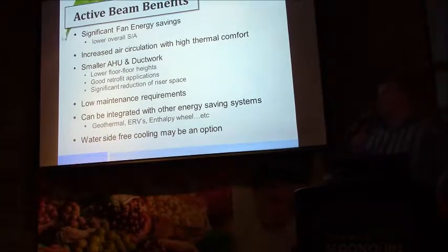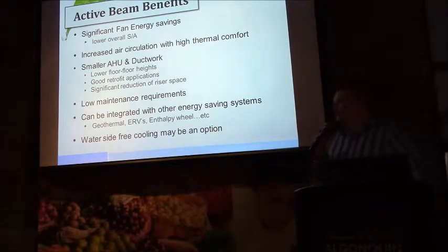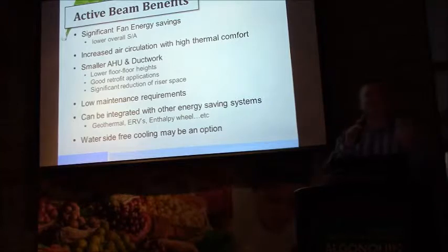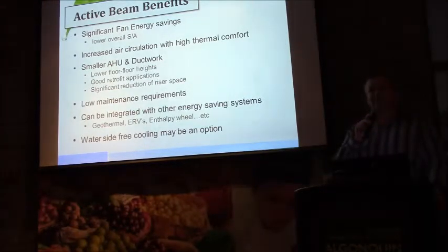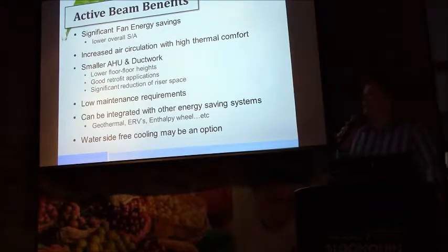And frankly, very affordable. Beams today are running neck and neck in terms of installed costs with a conventional fan coil system. There are exceptions to that, of course, in terms of controls. The more elaborate the controls, obviously, the larger the cost, and the more control resolution that's required on the space can also obviously drive up the installed cost. But a very attractive option for institutional-based applications, given that the district cooling is often in situ. It's on the site to begin with.